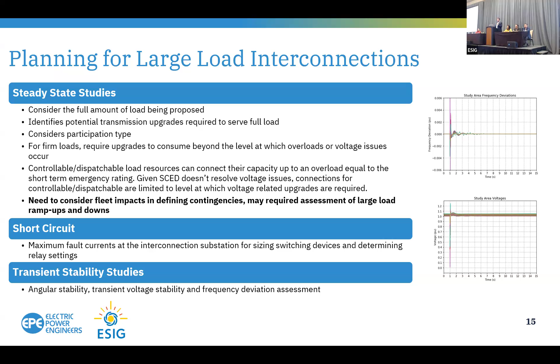So I do want to touch on voltage ride-through, and I'm sitting beside a colleague from Texas, where at ERCOT I think has really been pushing this as far as possible. I think recently at one of the large flexible load task forces, there was a moment of pause where I think the developers and the team got as far as they could without any help. And I really applaud the ERCOT team for getting things that far. There are a lot of concerns around voltage ride-through. I think we had an example in the PJM territory recently where for an out of zone fault, 1,500 megawatts of load tripped off out of zone on its own.